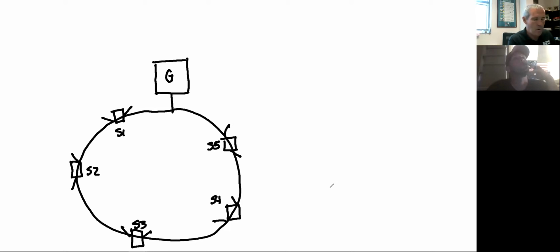Are there any open points? Do I have any O's? No, so I've got breakers on each side of my substation, but I have no O's. Is this system radial or looped? Looped. For one, you got a big loop in it. Transmission is normally looped.